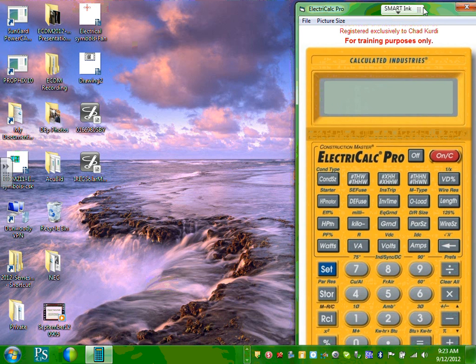For this boy. Before you start, obviously everybody knows how to turn it on, right? Cool. I'm starting from the beginning. Turn it on. The most important thing is, like everything else, garbage in, garbage out. Very, very important before you start. When you start anything, can you guys see three-phase 60? That's the temperature, and CU for copper. Anything you do right now, conductor-wise, it's taking into consideration three-phase, copper, and the 60 degree column. Would that screw you up really big when you start sizing based on 75? Okay, that's the most important thing.